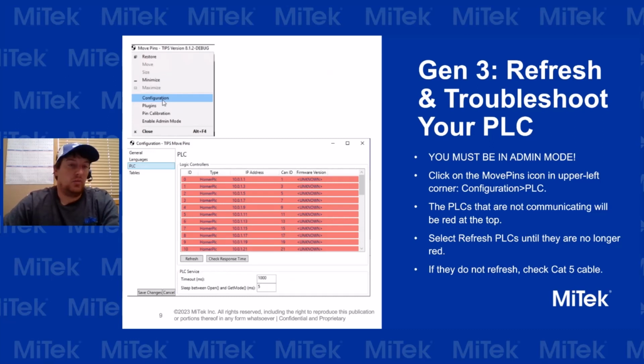If they don't refresh on the first one, give it a couple more clicks. Sometimes it just might be taking a little bit of time to read. The computer's reaching out to each PLC saying, "Hey, are you awake?" And it might take a little bit of time to wake them up. If after 4 or 5 clicks it doesn't seem like it's wanting to communicate, it's just the Cat5 cable could be bad going from it, or could be unplugged from that box.